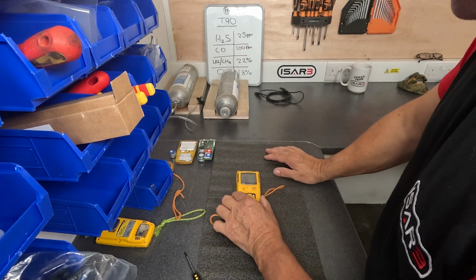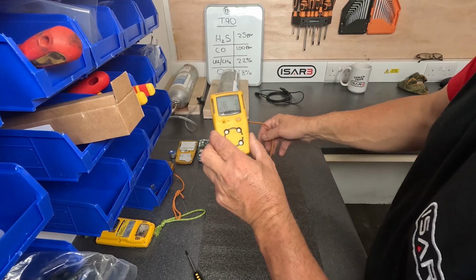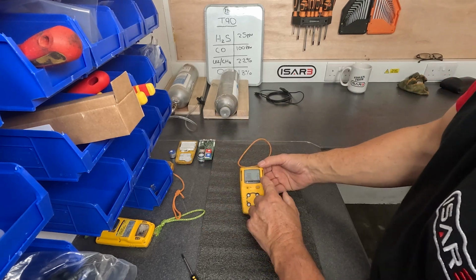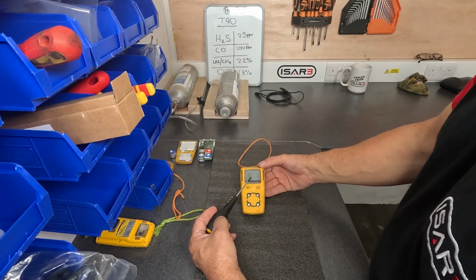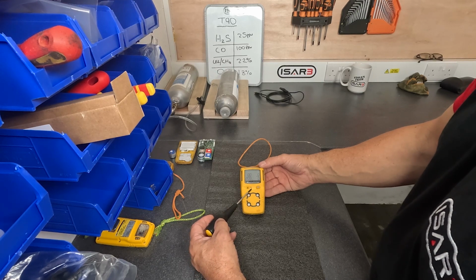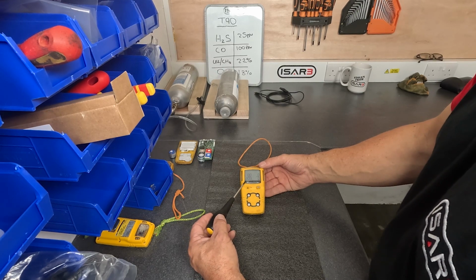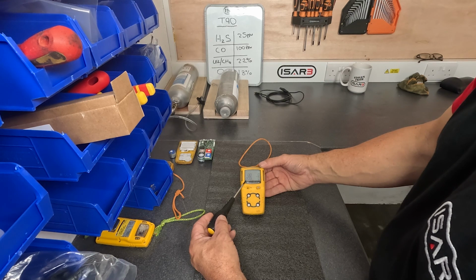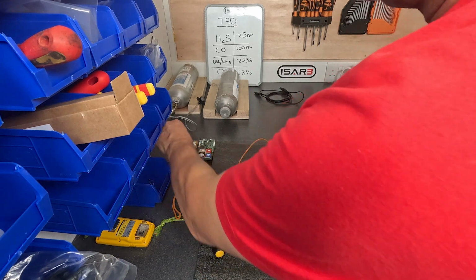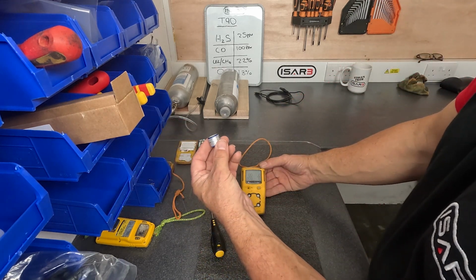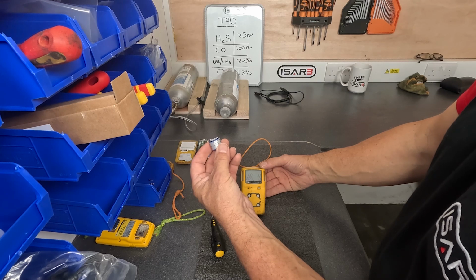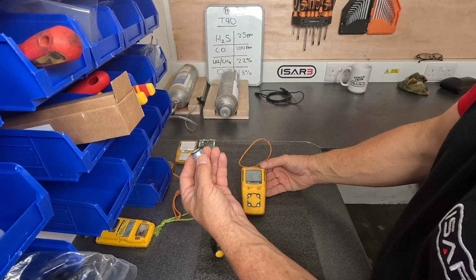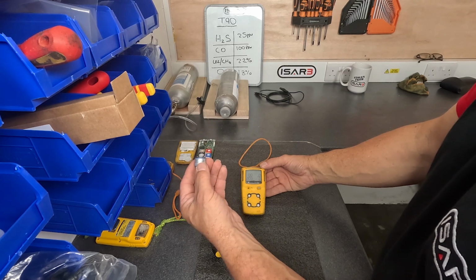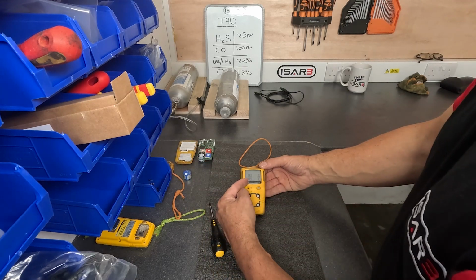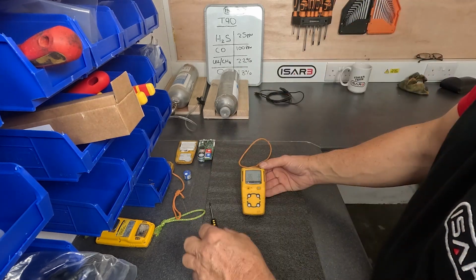But bump testing is the only way that we can verify out on site that all of these four sensors are working. When you do your fresh air startup, which of course you need to do outside in clean air, you will effectively auto zero the oxygen sensor, which is this one here, because that's the sensor that is constantly consuming itself. It's usually seeing oxygen all the time, so it goes out of specification. It's an electrochemical sensor, so you just reset that on startup by the auto zero process.